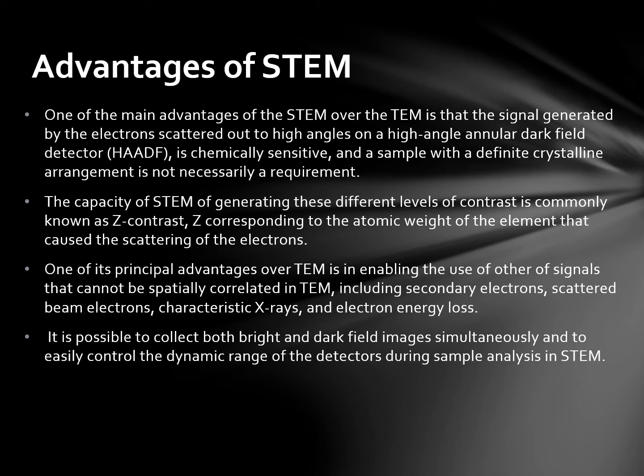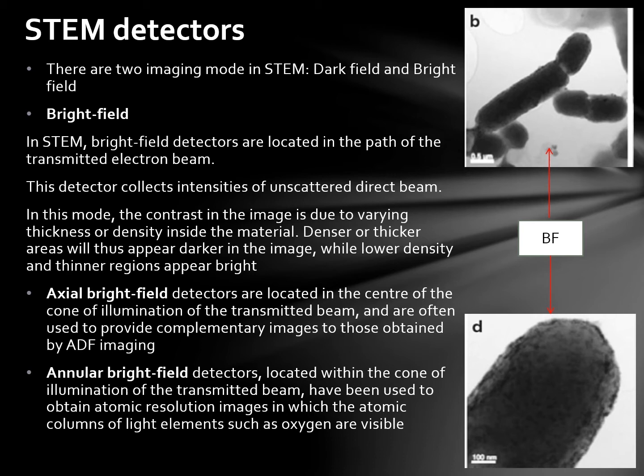There are two imaging modes in STEM: dark field and bright field. In STEM, bright field detectors are located in the path of the transmitted electron beam and collect intensities of the unscattered direct beam. In this mode, contrast in the image is due to varying thickness or density inside the material. Denser or thicker areas appear darker in the image, while lower density and thinner regions appear bright. Bright field detectors located in the centre of the cone of illumination of the transmitted beam are often used to provide complementary images to those obtained by ADF imaging.